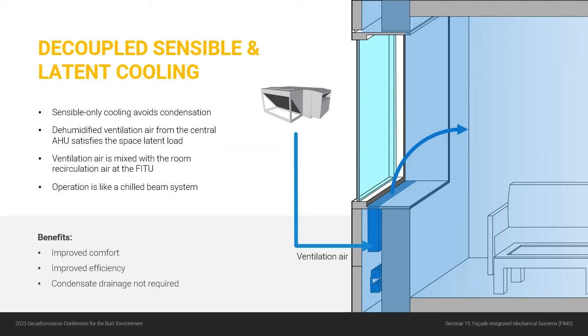So now we're going to talk about cooling, because cooling is a little more tricky than heating because we have to worry about humidity as well as sensible loads. And so the way to make this system work is to decouple the sensible from the latent cooling. So at the FITU, we're doing sensible cooling only. We're not forming any condensation. And we're relying on the dehumidified ventilation air to control the humidity in the space.